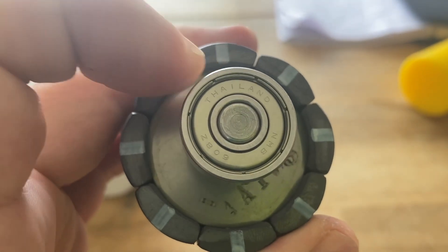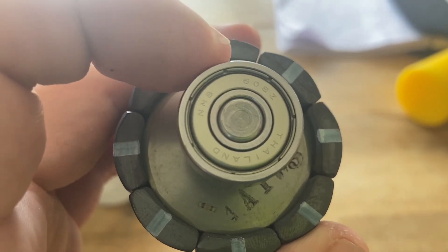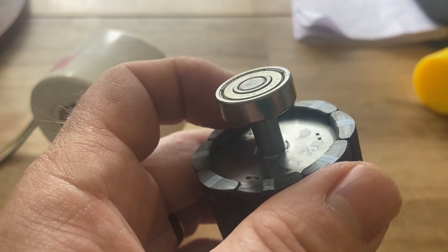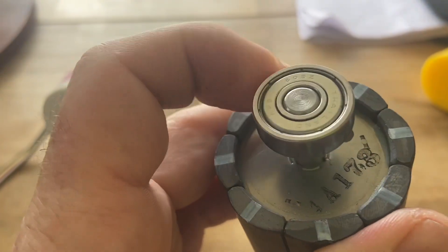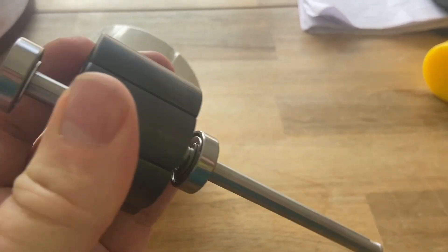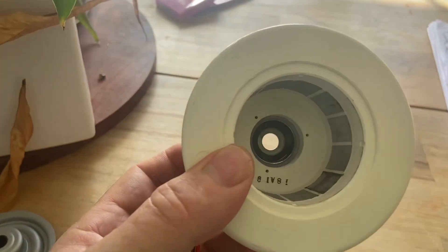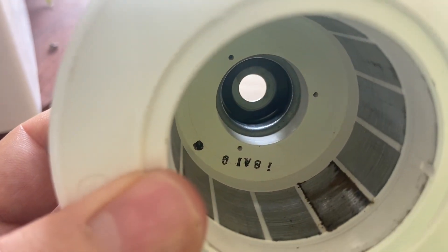You can see the type of bearings this particular motor has. This is out of a six kilowatt, and because everything's nice and clean on this particular example, these bearings will actually slide out with my hand. I can actually pull this on the shaft and out inside the motor.